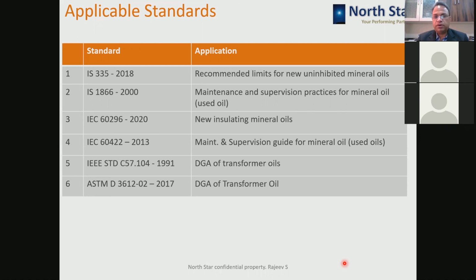Then IEC 60422, which is again a maintenance supervision guide for mineral oils, that is used oil or the oils which are available inside the equipment. Then there are standards like IEEE C57.104-1991, which is for the DGA of transformer oils to understand the trend of the gases inside the transformer. So IEEE C57 is referred, and ASTM D3612-2017 version is again for understanding the DGA of transformer oil.